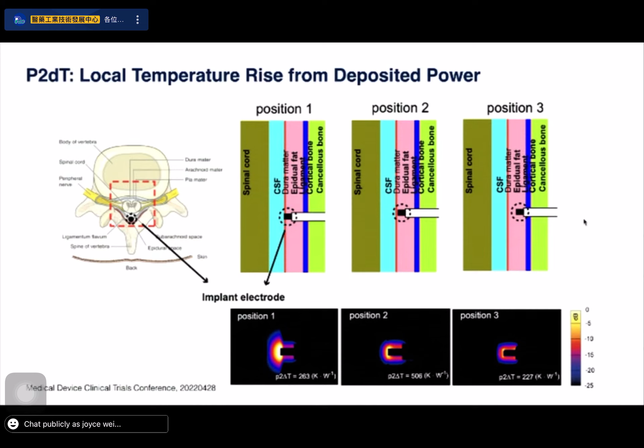Another portion, which I talked about briefly with the candle example, is the temperature rise, which is necessary to estimate. And what we consider even more important is something that's called thermal dose, or CEM43, cumulative equivalent minutes at 43 degrees Celsius, which is a number that differs for every tissue and determines when the tissue is actually damaged or not.